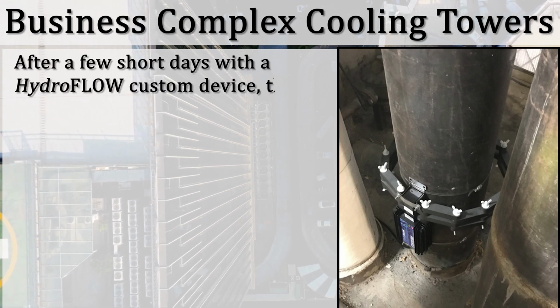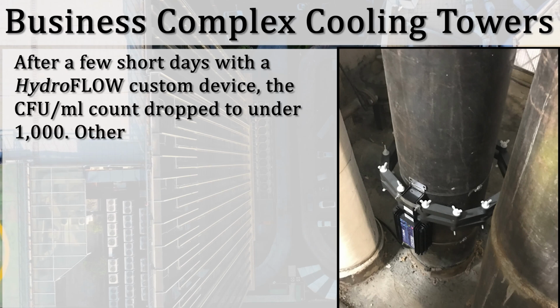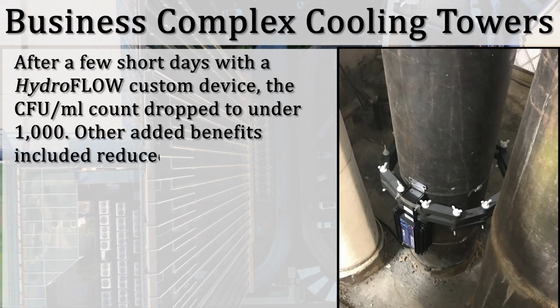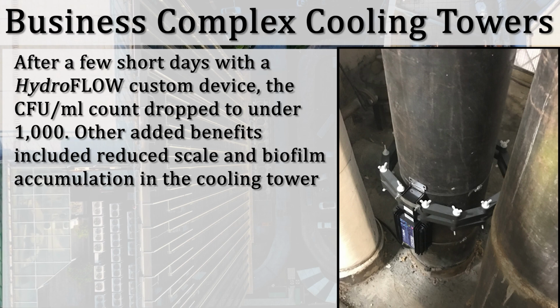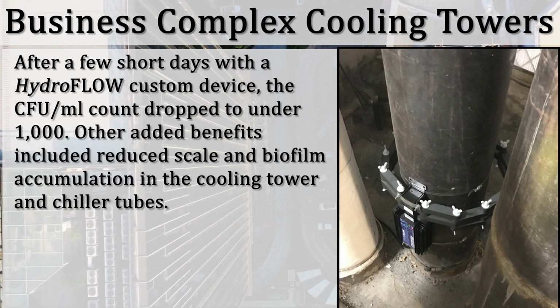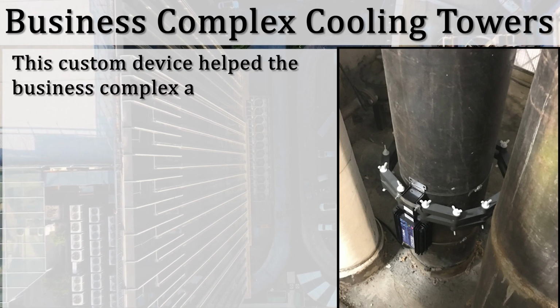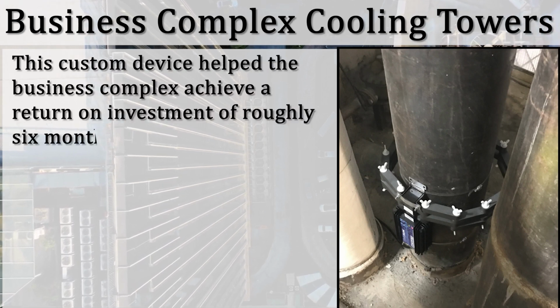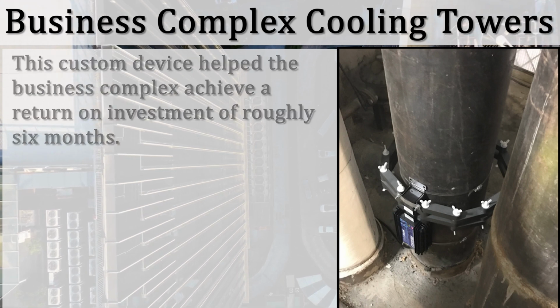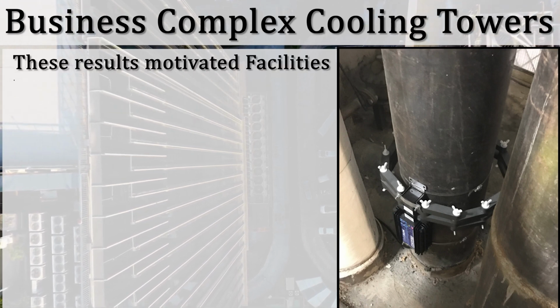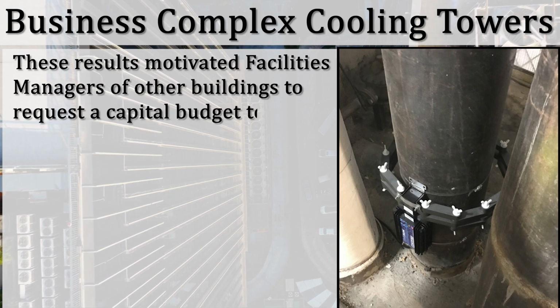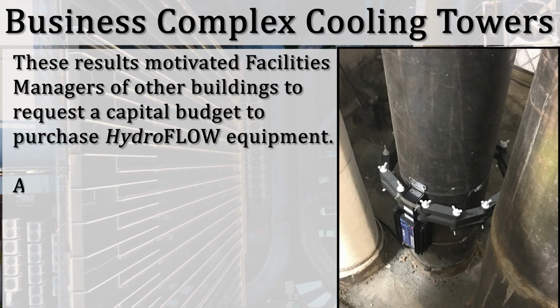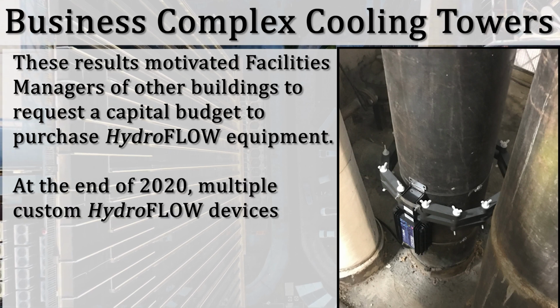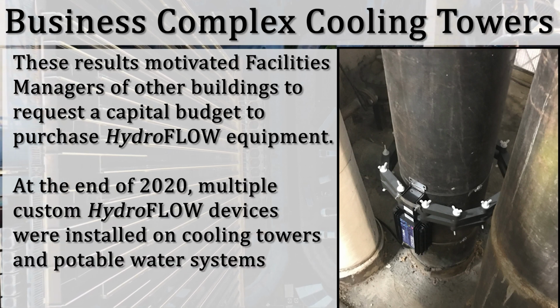Results: after a few short days with the HydroFLOW custom device, the CFU per milliliter count dropped to under 1,000. Other added benefits included reduced scale and biofilm accumulation in the cooling tower and chiller tubes. This custom device helped the business complex achieve a return on investment of roughly 6 months. These results motivated facilities managers of other buildings to request a capital budget to purchase HydroFLOW equipment. At the end of 2020, multiple custom HydroFLOW devices were installed on cooling towers and potable water systems throughout the complex.